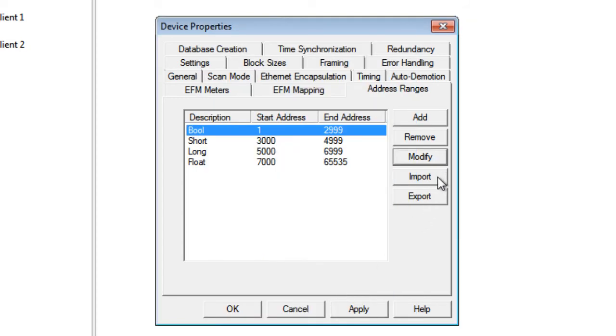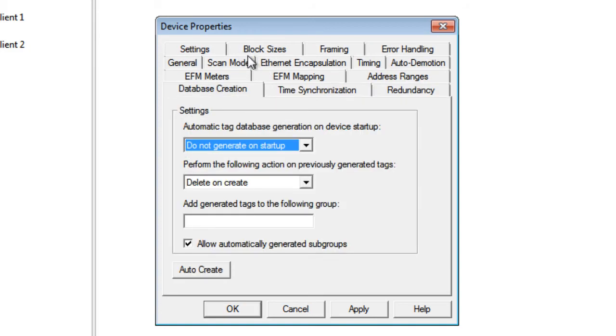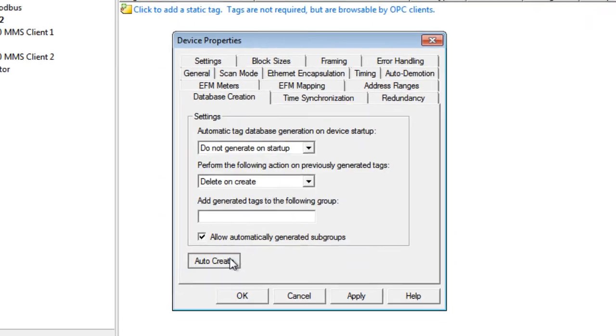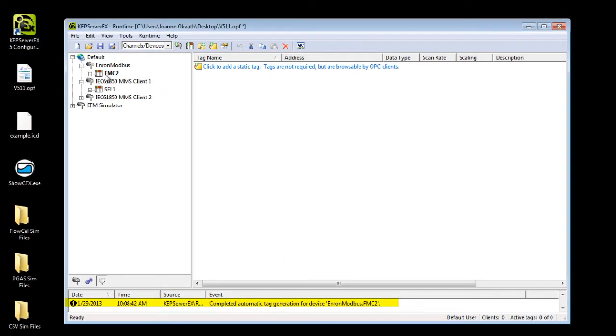The export and import options allow address range configuration using the CSV file format. With this enhancement, the Enron Modbus driver can work with devices that do not use the standard Enron address extensions. Finally, the EFM configuration tags may be automatically generated for the Enron Modbus driver without being connected to a live device. Go to the Database Creation tab and click Auto-Create. This allows users to validate their configuration mapping.